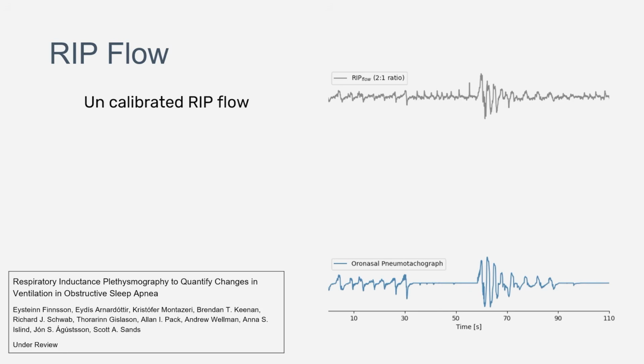The black trace up here is just what we call uncalibrated RIP flow. So you just take the signal from the abdomen and the chest, you add them together, and you get a flow signal. And the blue trace here is oronasal pneumotachography, so really the most accurate measurement of flow that we could have. And what we see is that during the apnea, the RIP flow signal still shows some spikes.